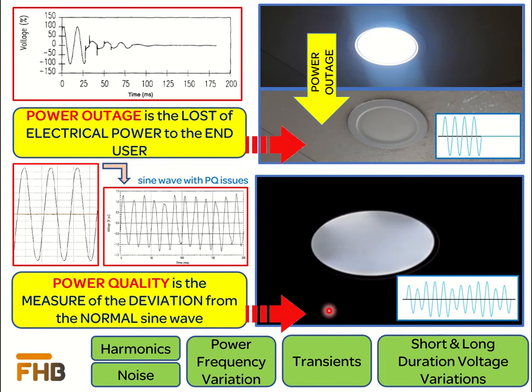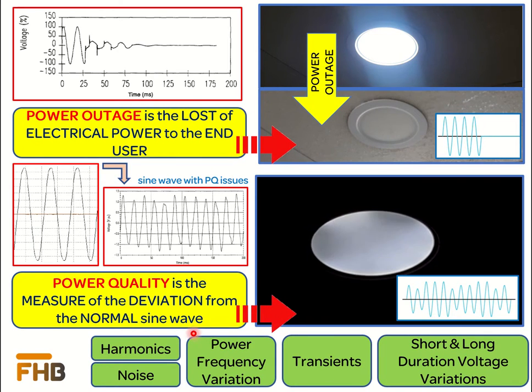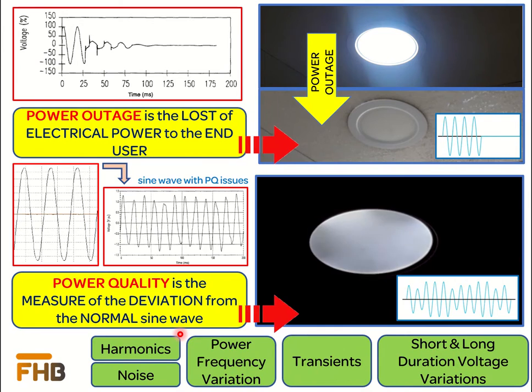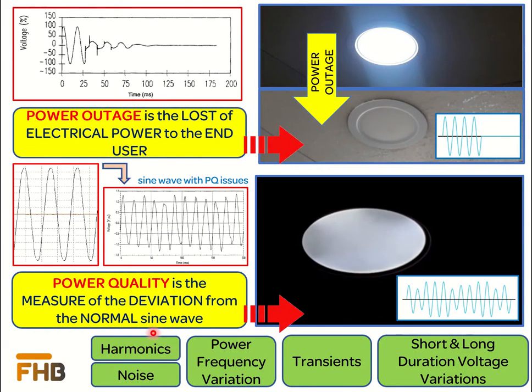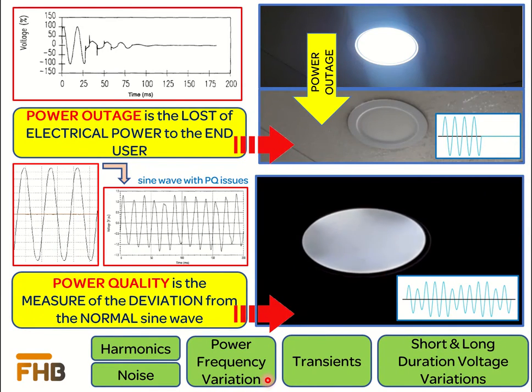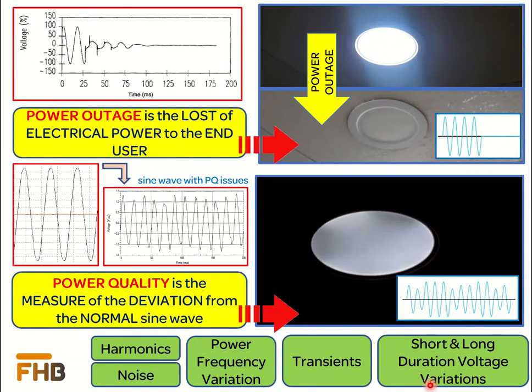Under the definition of measurement of power quality, we can refer to a wide variety of phenomena that characterize the voltage and current at a given time and at a given location in the power system. These phenomena can be waveform distortion due to the presence of harmonics and noise, power frequency variation which is directly related to the speed of the generators, any transient in the power system such as due to lightning effect, or it can also be different short and long duration effects of supplied voltage.